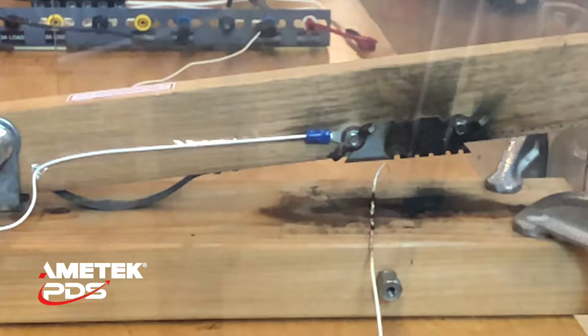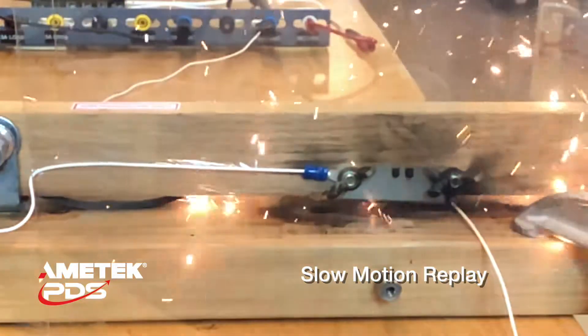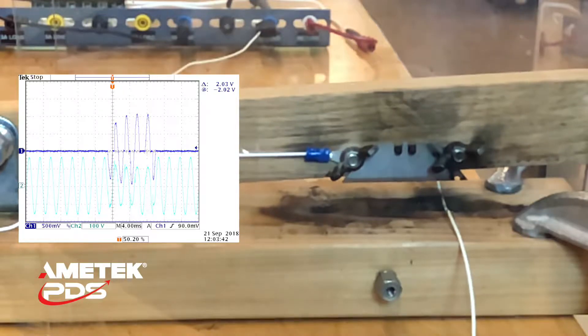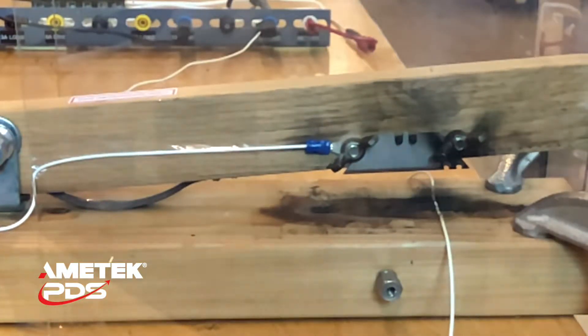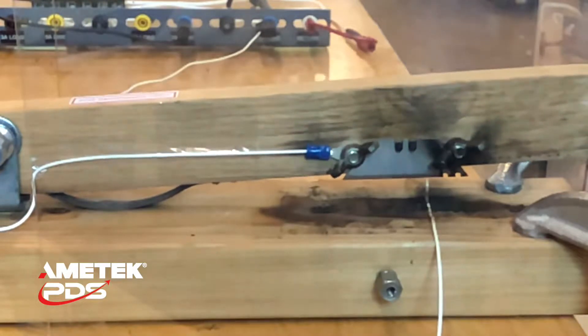Go ahead and take a look at that blade. We've basically destroyed the wire and vaporized the sharp end of that blade. We're looking at 500 amp current peaks on this scope — multiple 500 amp spikes. Remember, this is AC, so it crosses zero once in a while. The thermal breaker gets some benefit of the voltage crossing zero, but still it took at least five of those damaging strikes.